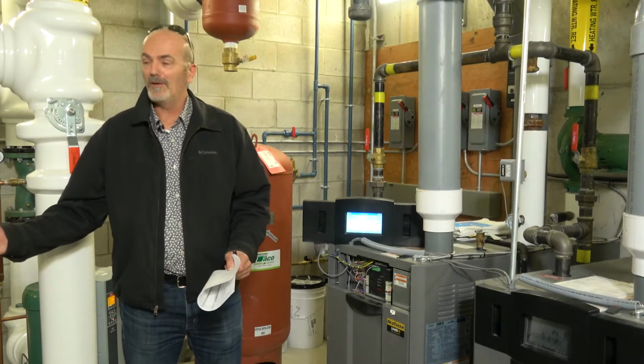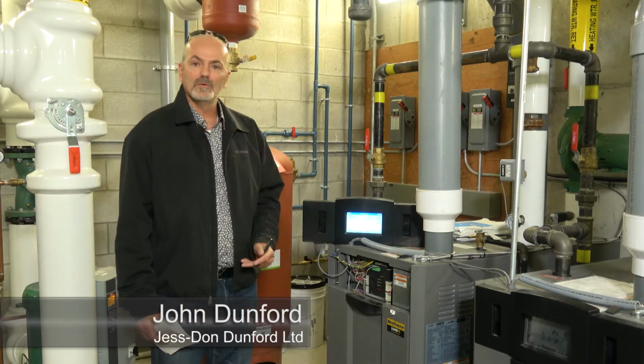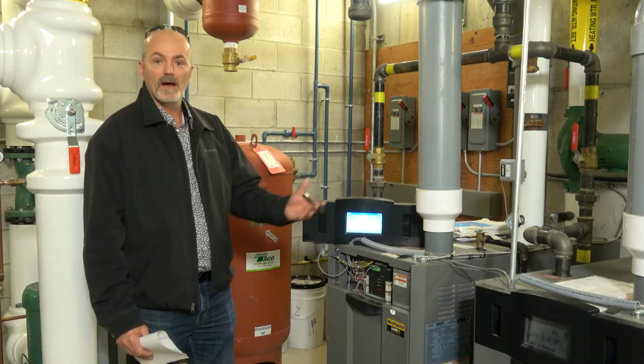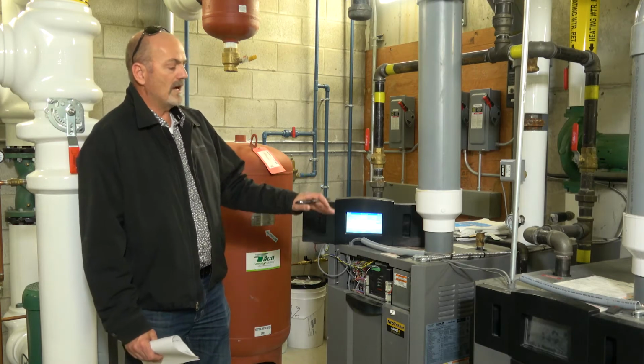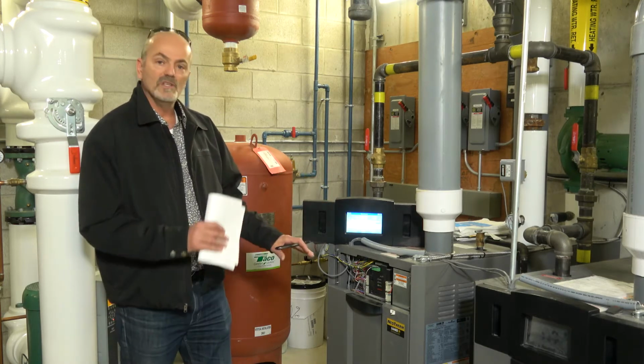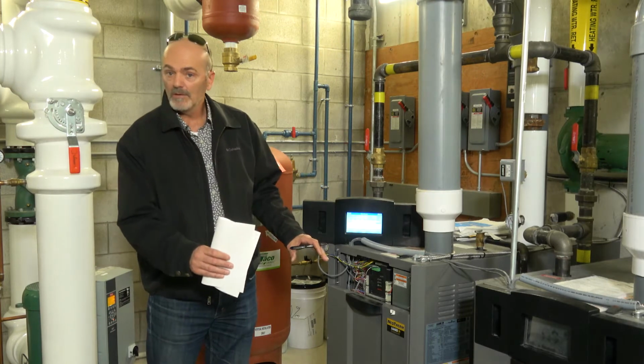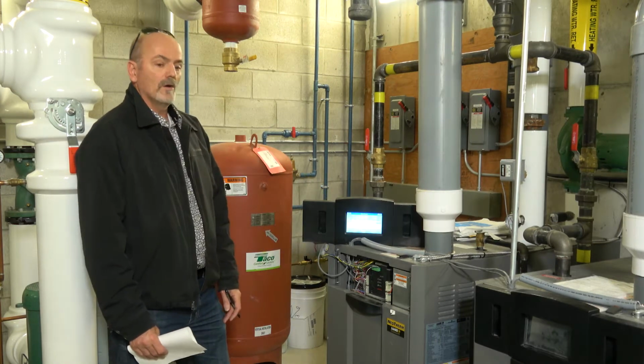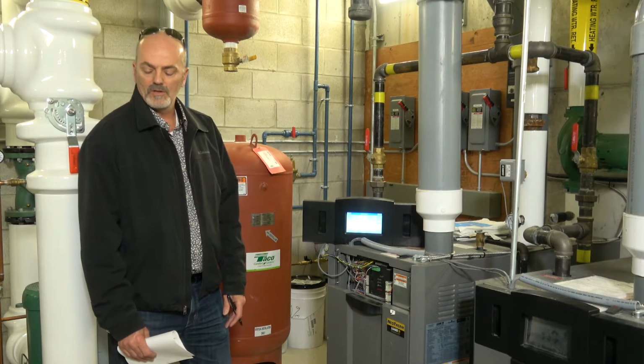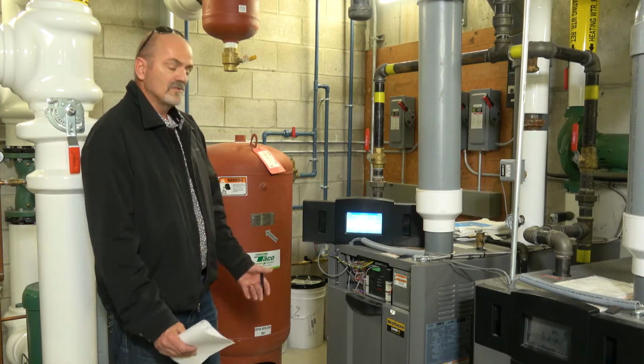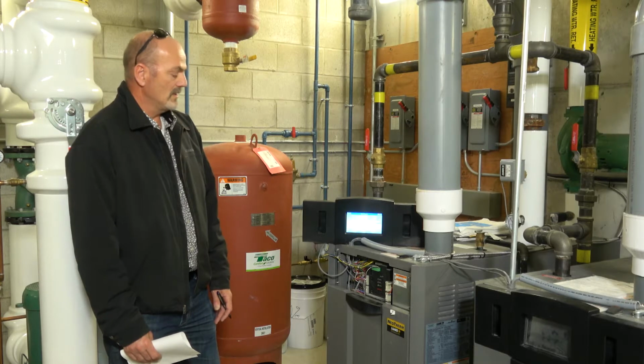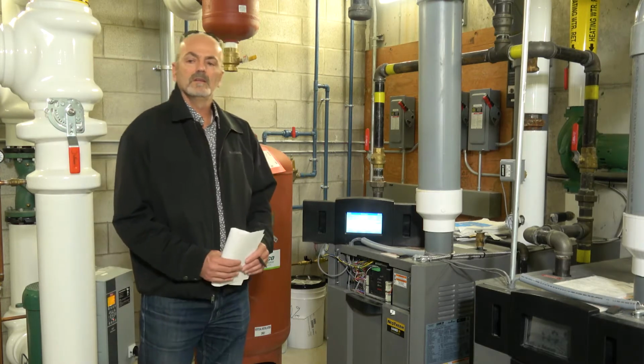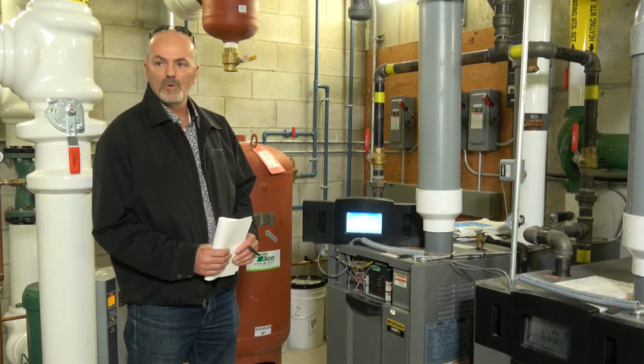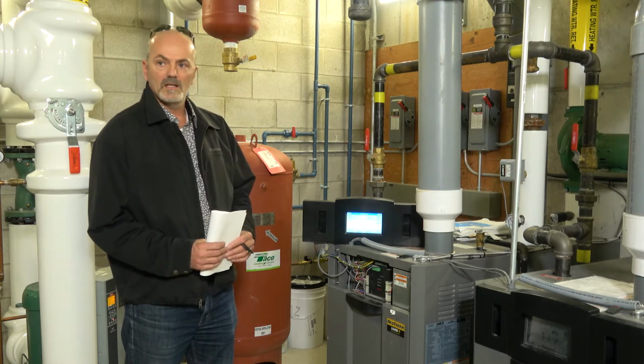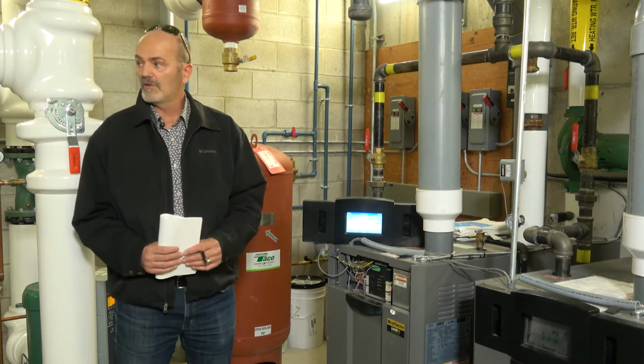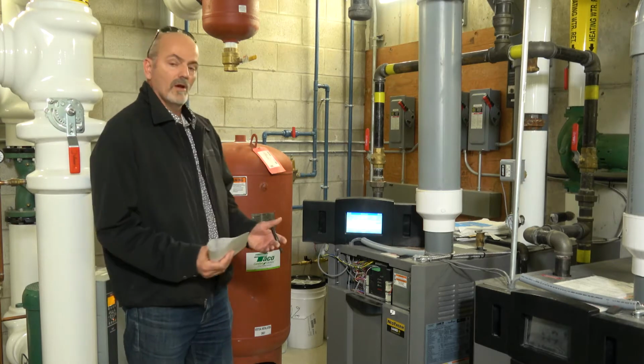For maintenance personnel on staff, this is a quick review of the boiler system. There are 2 boilers in a master slave, duty standby arrangement, where one backs up the other. Because they are gas appliances, working on them or dealing with any issues requires a licensed contractor with both a TSSA license and a gas fitters license, who has familiarity with the boiler.